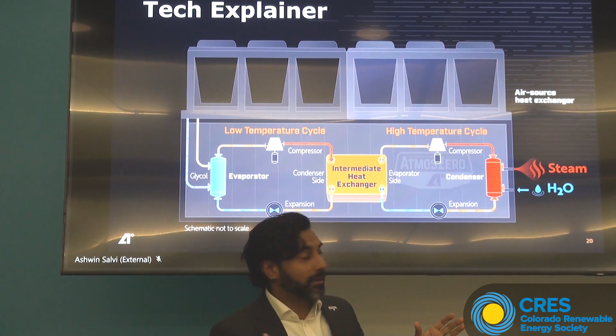The reason we split it is that instead of using one cycle, we can fine-tune the thermodynamics. There's not a good single refrigerant with the best efficiency or commercial availability to go all the way from ambient to steam temperature. By splitting it into two, we can use one refrigerant here and a different one there, each with properties best suited for that temperature range, giving us the best efficiency possible.